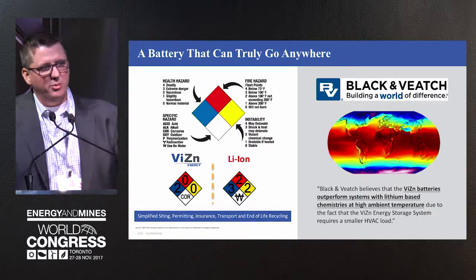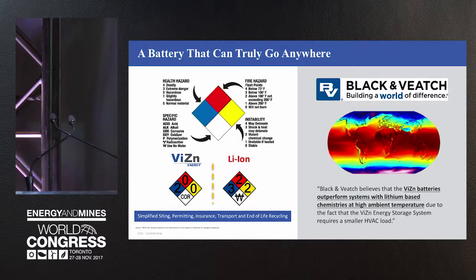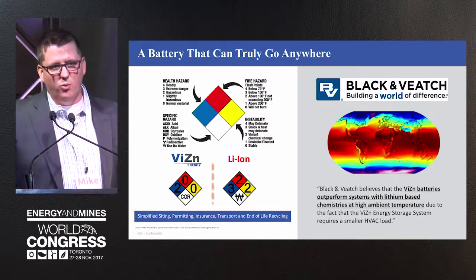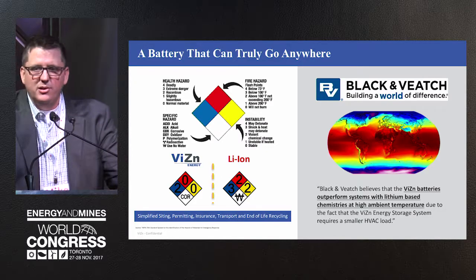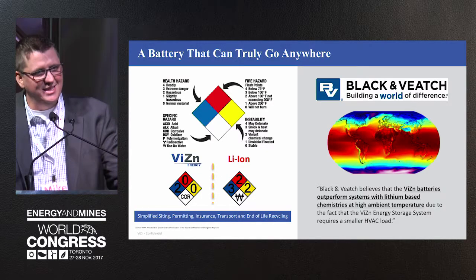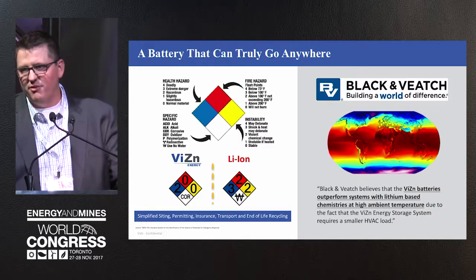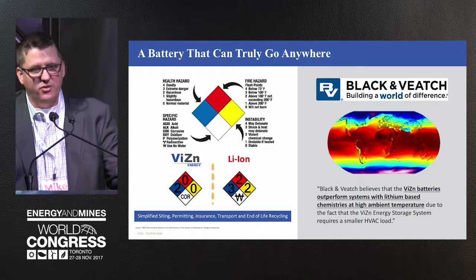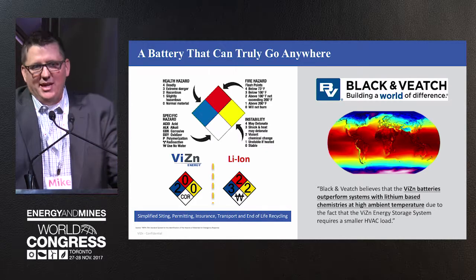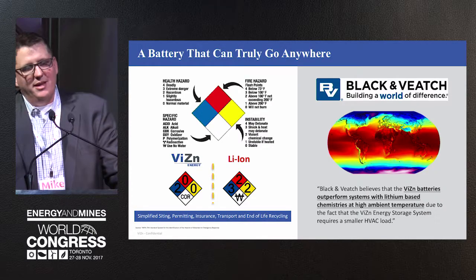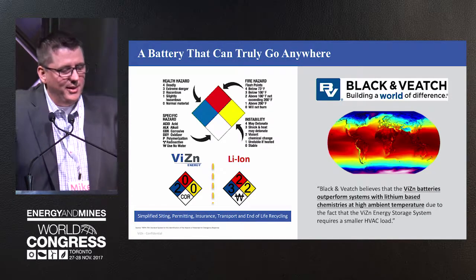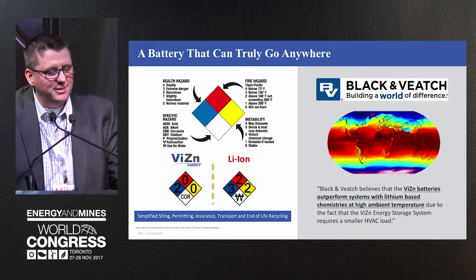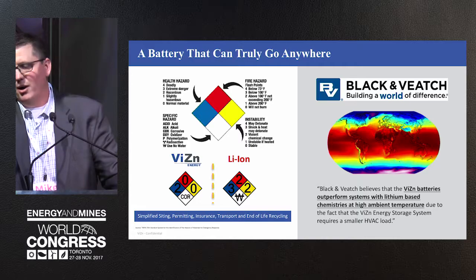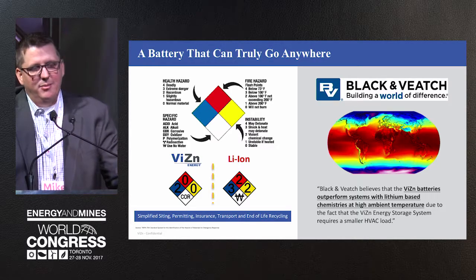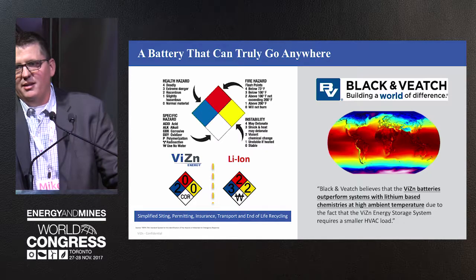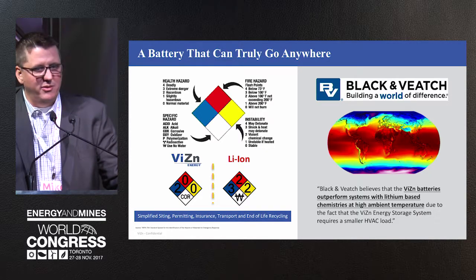They'll look you in the eye and say round trip efficiency is in the low 90%. However, when you account for a warm weather site and load in all these aux loads, round trip efficiency on the AC side - kilowatt hours traveling in and out of the inverter - is really in the 78 to 82% range for a warm site. That's one of the key nuggets of the Black & Veatch report on ViZn's technology: they believe our systems outperform lithium-based systems at high temperature because we require zero HVAC. Our batteries run at 130 degrees Fahrenheit, and the aux load is relatively negligible.